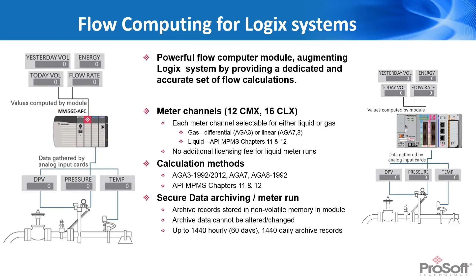And then again, when we talk about configuration and monitoring software, as we worked with individual producers, it became very apparent that producers didn't want all their instrumentation and measurement guys having to become PLC experts and going in Studio 5000 to make changes. And so we created a standalone configuration software, which can connect via Ethernet or serial port on the module. And it allows your measurement and your instrumentation group to do the specific functions related to measurement without having to go online with Studio 5000. So everything from meter configuration to site configuration to just monitoring the data, looking at what your flow rates are, what your accumulators are, going in and looking at the archive data.